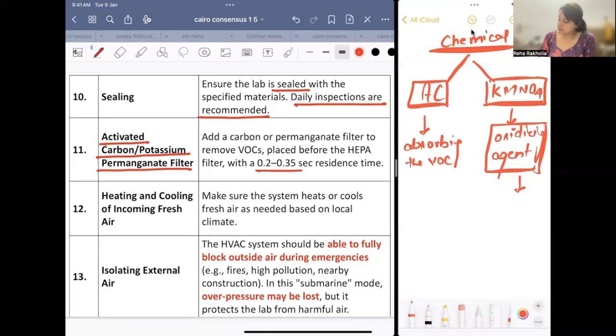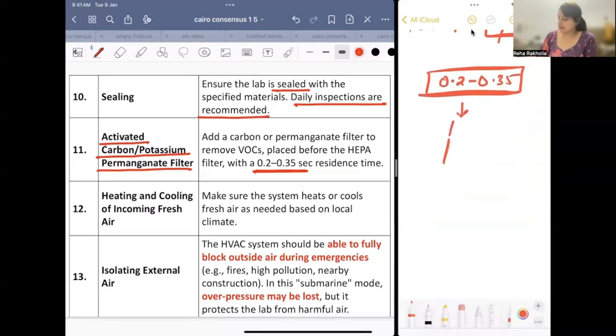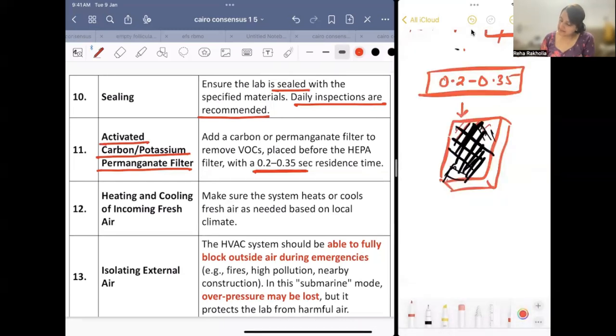The residence time is 0.2 to 0.35. What is residence time? Residence time is for how long air stays in contact with the filter material. Like this is the activated charcoal and KMnO4 filter, so we see for how long air has stayed in this filter. It should be 0.2 to 0.35.